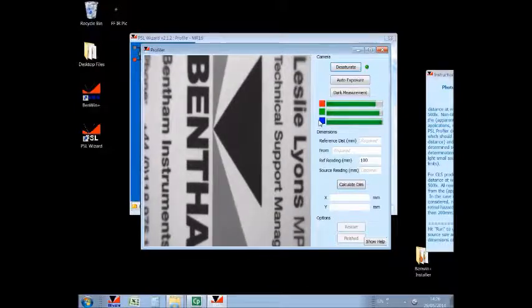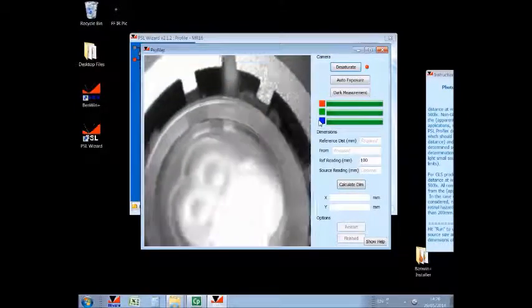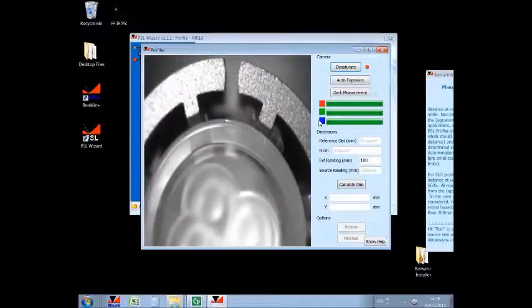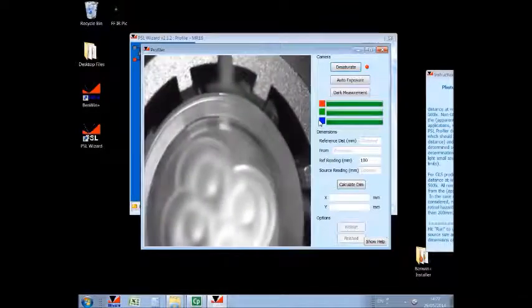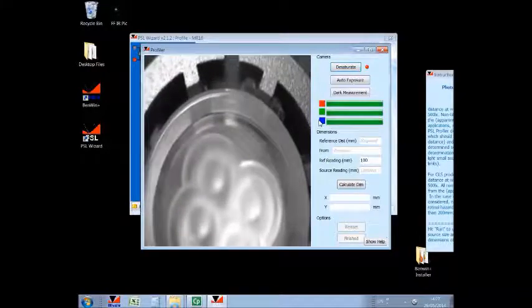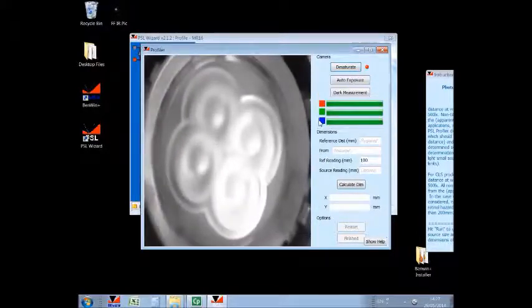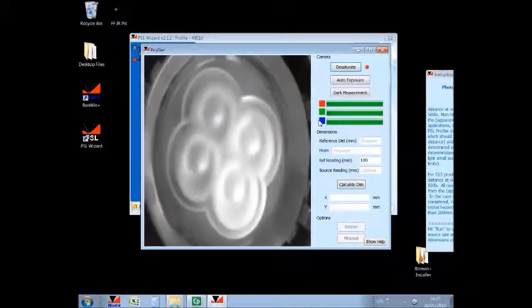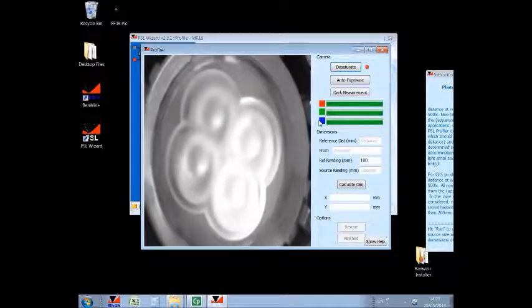At which plane we will now place the front surface of the MR16 source to be measured. And I will adjust somewhat the height to have it in view. Now, this source has a package which is somewhat diffusing. It is not really clear what the eye would image in the worst case where we want to view the source when on. But we will have a look at what we see on the screen. So we power the source on and we have clearly saturation.